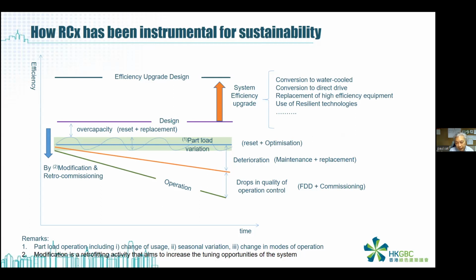And when you go downstream, below the purple line, there are problems when you operate the buildings. One of them is that most people over-capacity or over-design their systems or equipment because they want to play safe, so they would not design just in time. When equipment is over-designed, it will not be efficient, so we need to do some resetting and also replacement in order to make the equipment suit the operation. Also, in normal operations, because we have seasonal changes and operational changes, equipment may not always operate at full load or at rated condition.